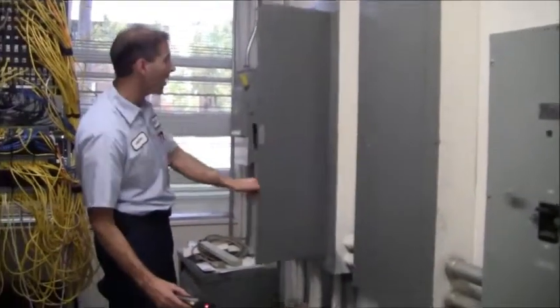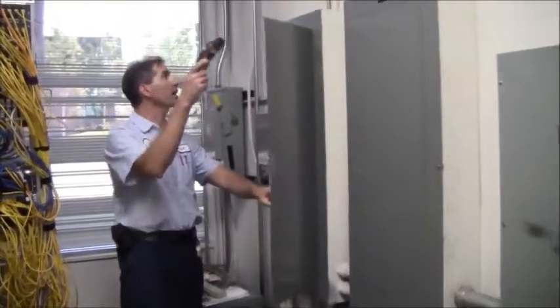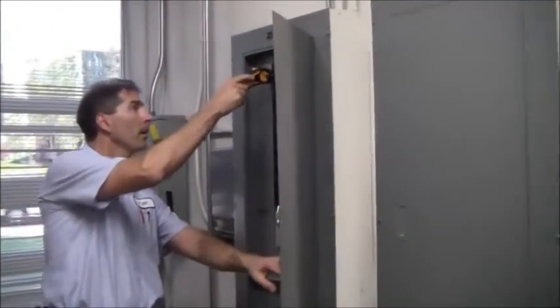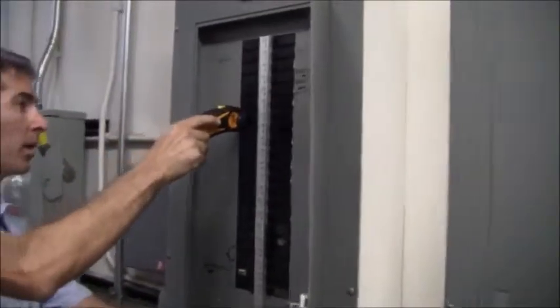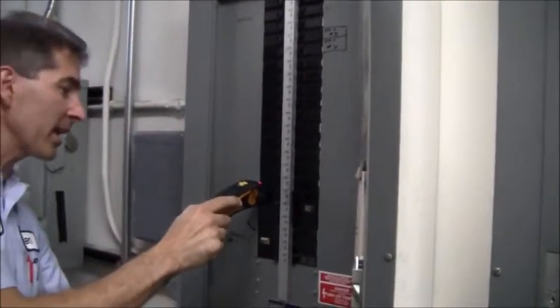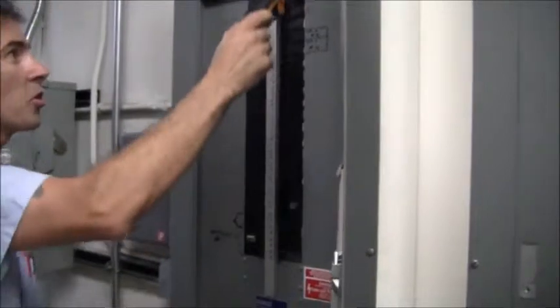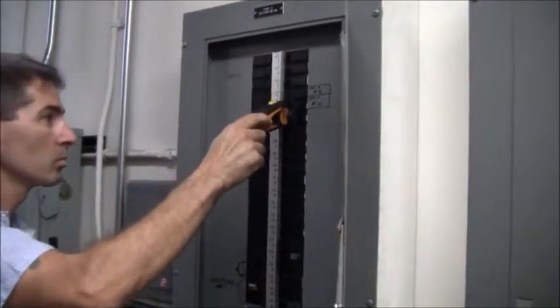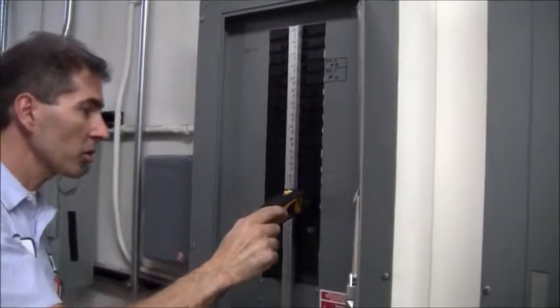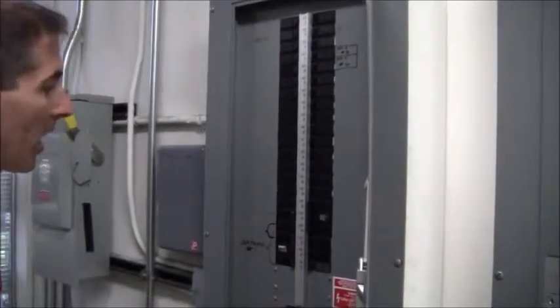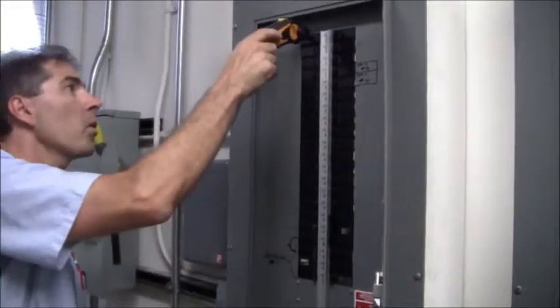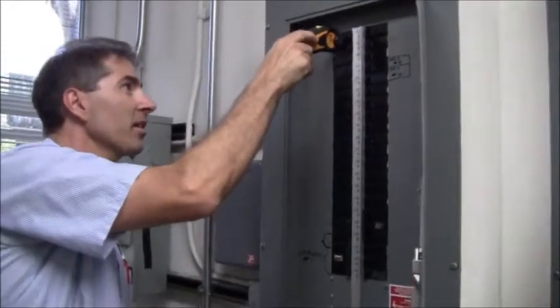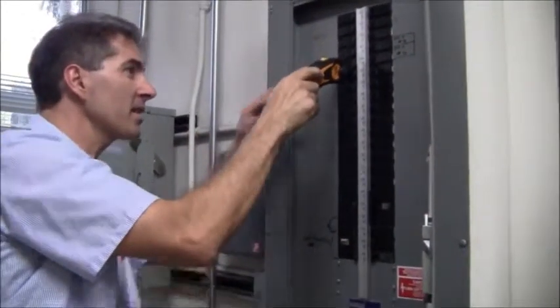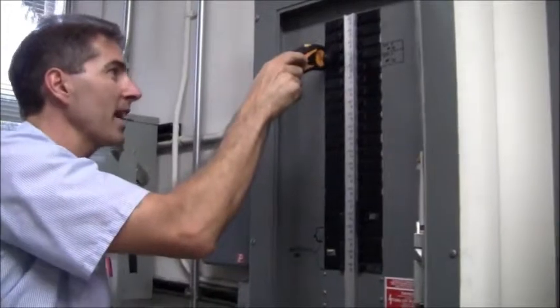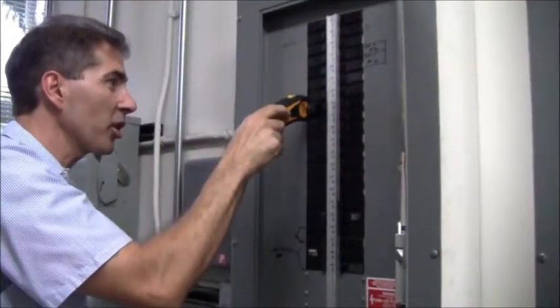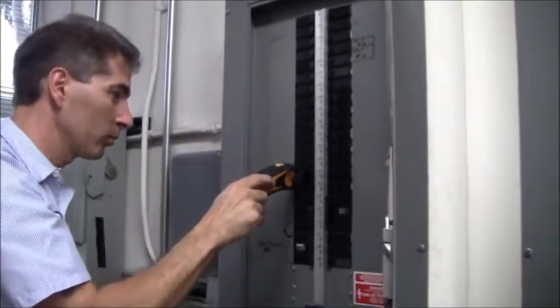I'm going to put this probe on and start at the top, working my way down. This should be making beeps all the way down, which is normal. So slowly I'm going to strike each breaker, then do the whole panel one more time. Every time it does this, the probe is so smart it knows exactly which breaker it is - it should only beep now at the right breaker.